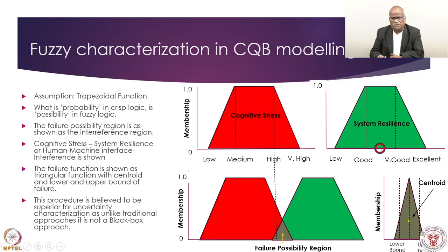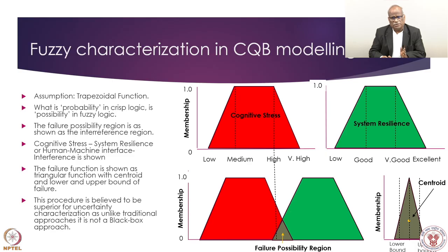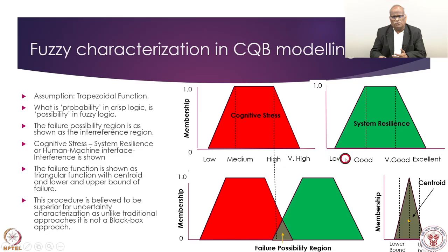However, if something happens — such as a subsystem failure — the interface quality can drop from excellent to very good, good, or low. Within moments, there will be an overlap. The complete emergency procedure should be characterized for each event, from the transient start through all actions taken to bring the plant to normal. One must identify where the system can switch states. For instance, if the control room loses power supply — even though class 1, 2, and 3 supplies are provided — a blackout-type situation makes the interface no longer good, and this must be addressed by control room designers.